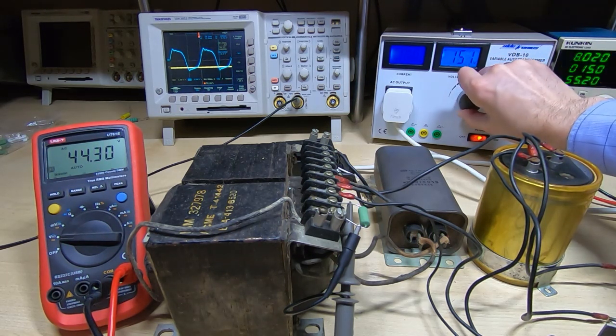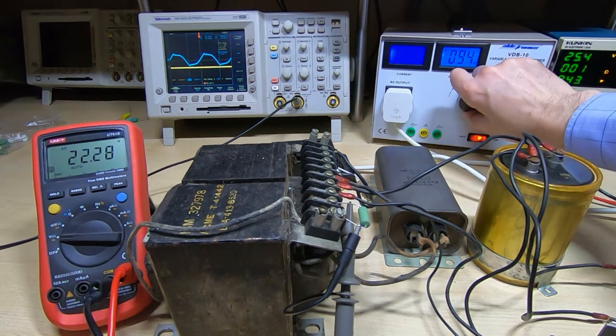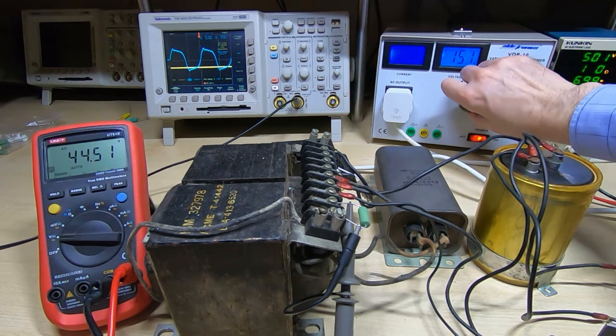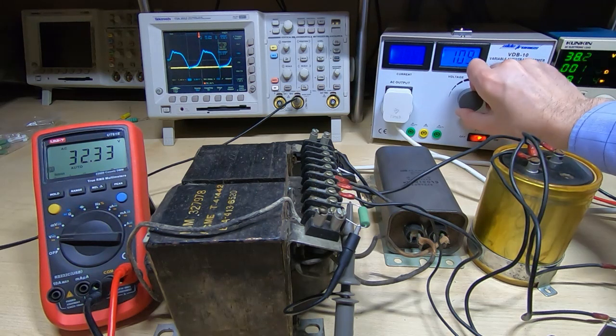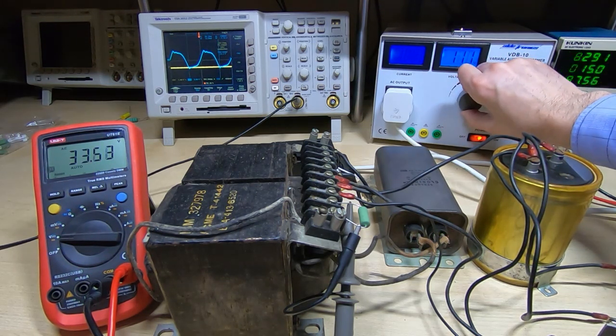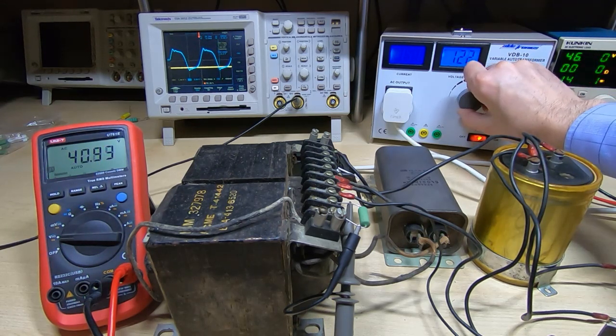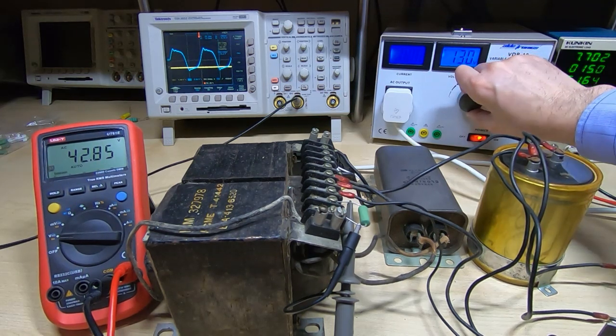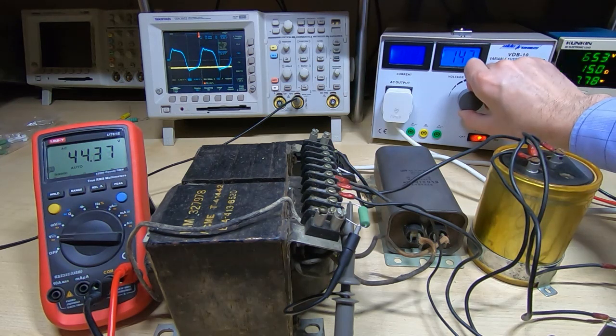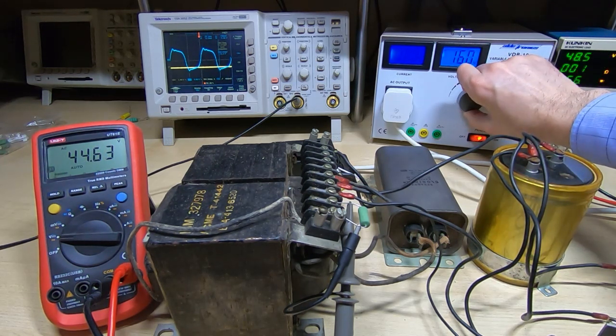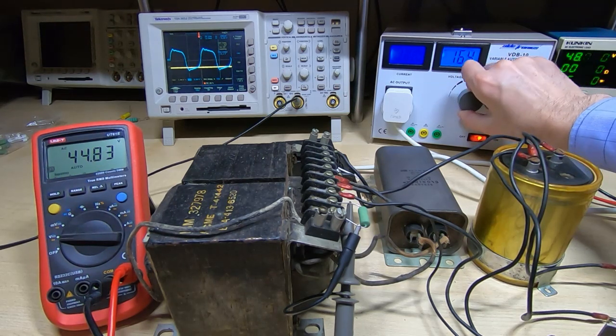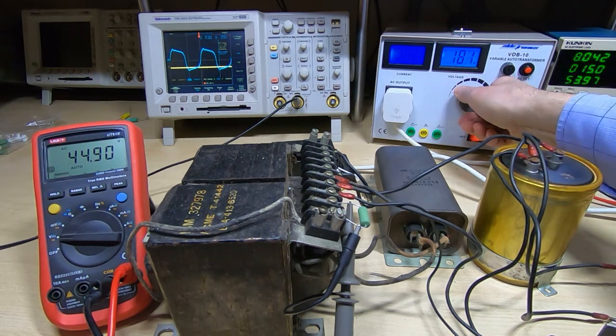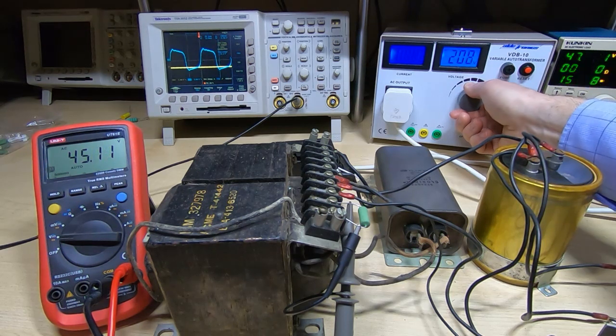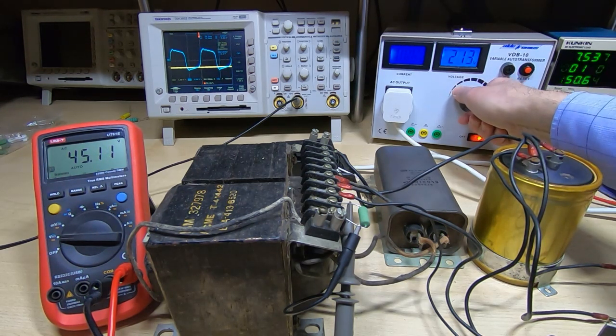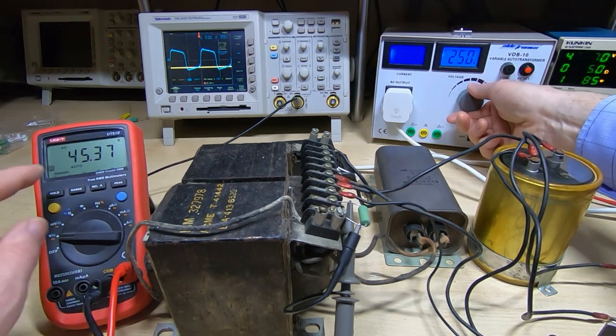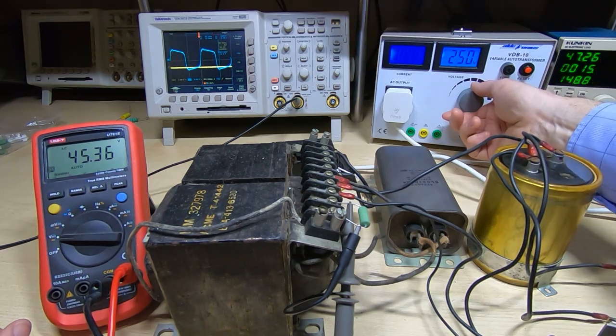of this resonant operation of the core and we'll actually turn back into what amounts to a sine wave. It's now not working as a proper ferroresonant transformer, but as we start to go back up we reach the point where the core is saturated, which is about there, and if we continue to go up, the output voltage cannot continue to rise much further because the core in the secondary region is fully saturated, and so the transformer can't give a higher voltage output than that. So that's about 160 volts where we reached that point. I'll keep going up, so we're now at 190 volts, but you can see that all that's happening is we're just running into saturation slightly sooner, but the actual output voltage is staying the same because the transformer is not able to provide a higher voltage than that.